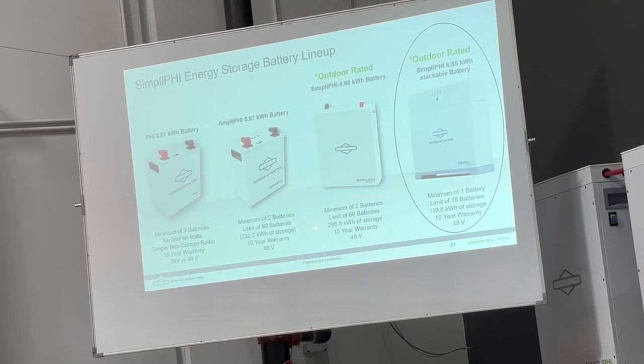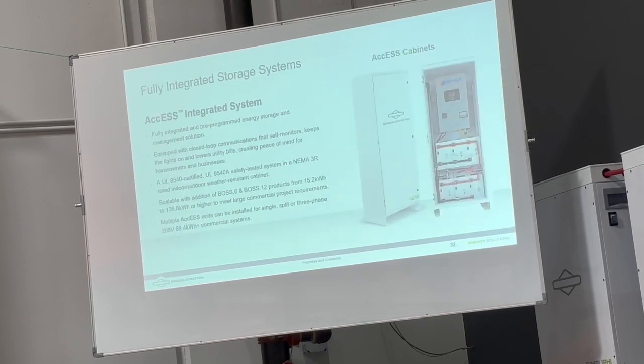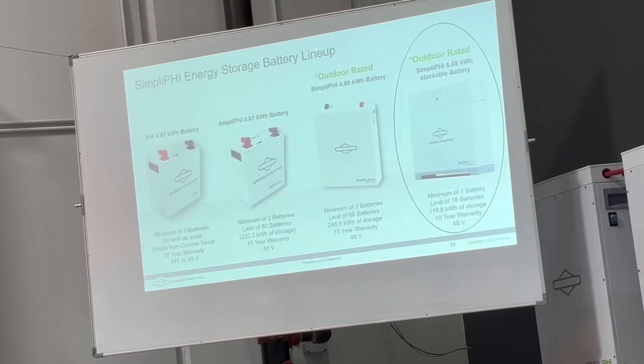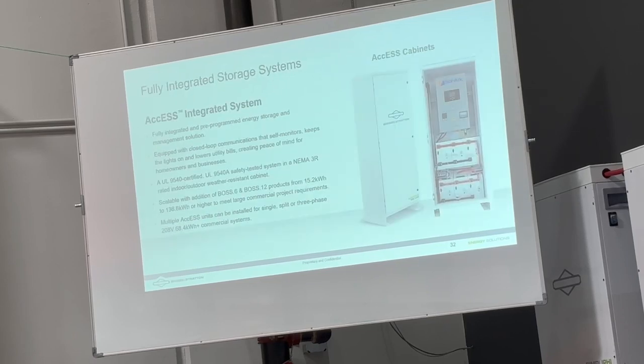We can build slightly larger systems with this. If you have a really big system, we actually recommend this SimpliPHI non-communicating battery, because your batteries can be on large bus bars, etc. I'll show you some examples where we've got a 100 battery system with 7 or 8 Sol-Arks paired up - some villages in Alaska, an island in Connecticut.